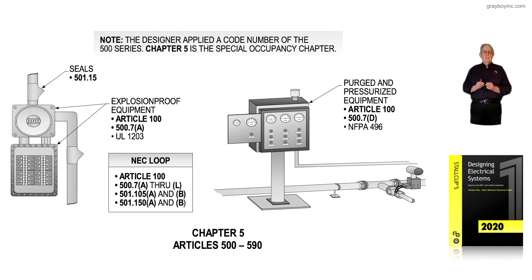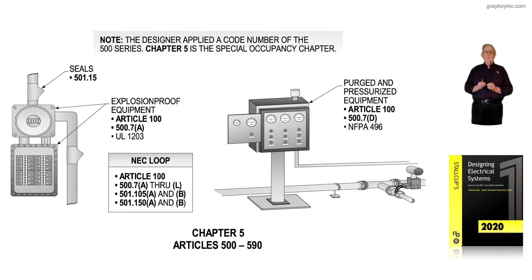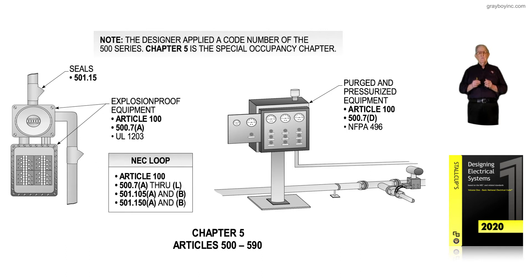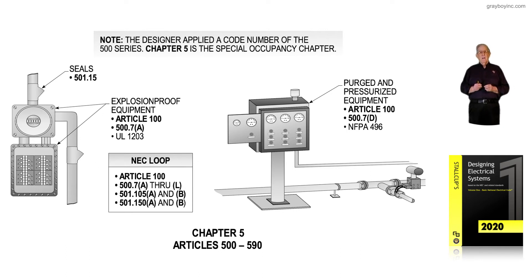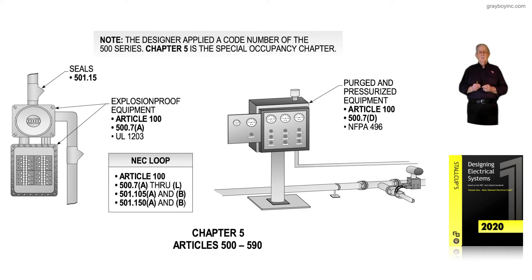If we wanted to take a Hoffman box and install hermetically sealed contacts or use nonincendive circuits, then 501.105A and B would deal with instruments or relays and things like that. And 501.150A would deal with communication circuits, control circuits, and those kinds of items.